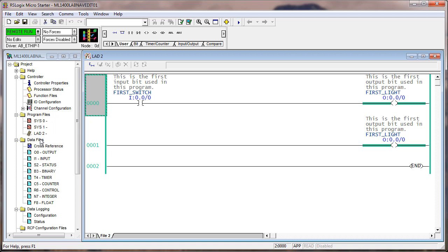You have to add something to get the program execution to go look at those other routines and run them. But for right now, ladder 2 runs automatically. So if you're in the run mode and ladder 2 is the only file, and that's the one you're looking at, and you see an instruction that's false but an output that's on, you have to know someone somewhere else is turning it on, whether you can see it or not.